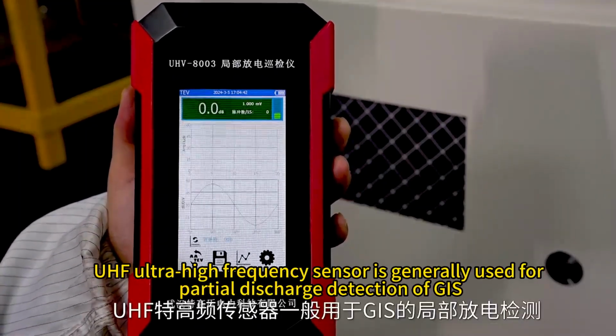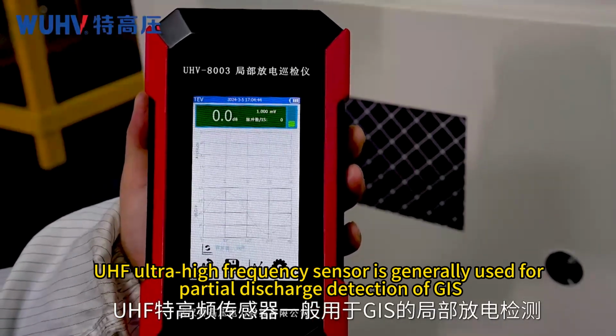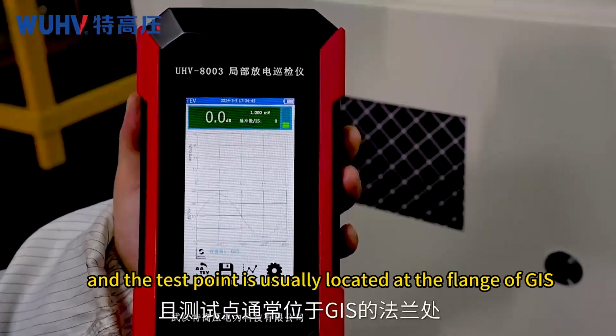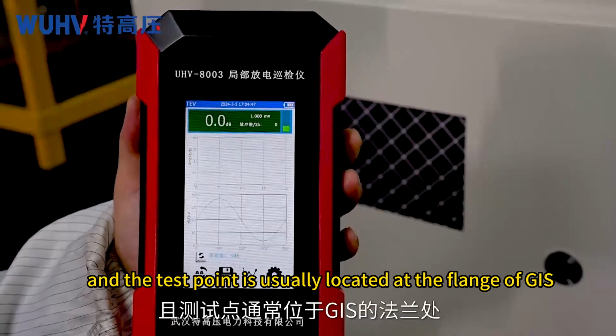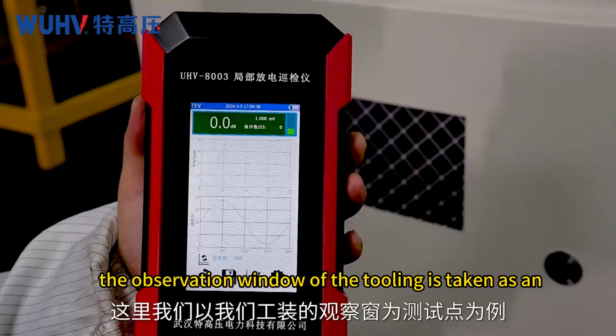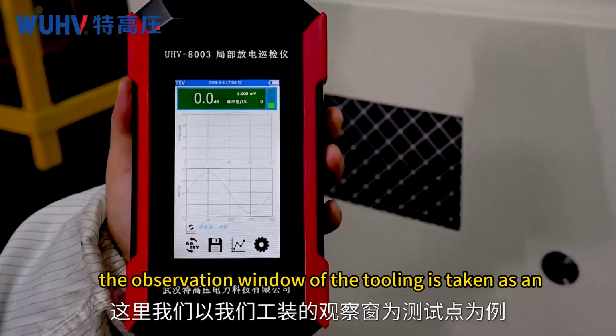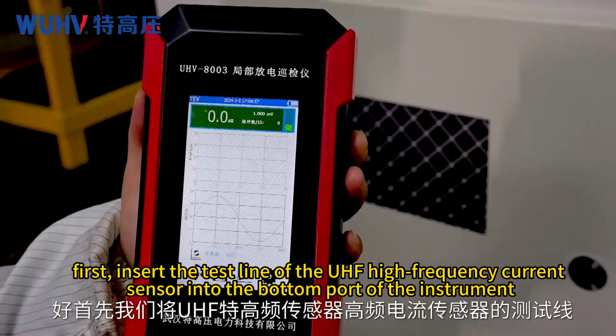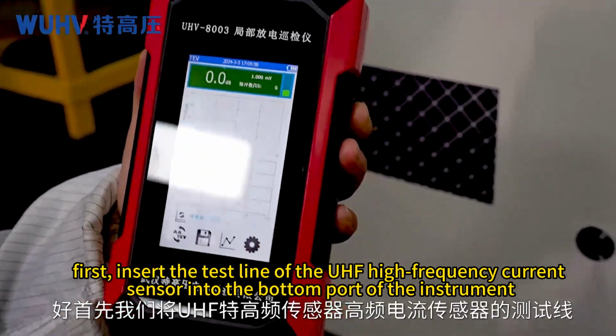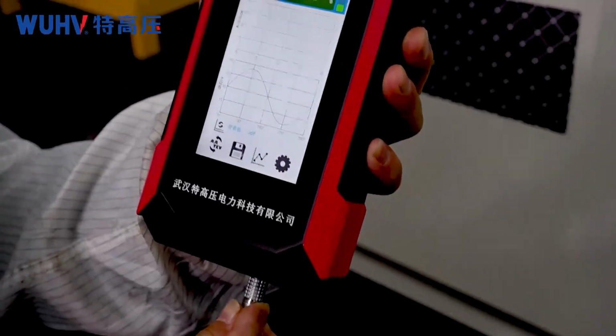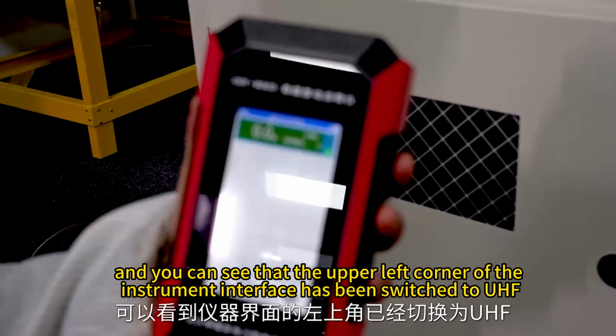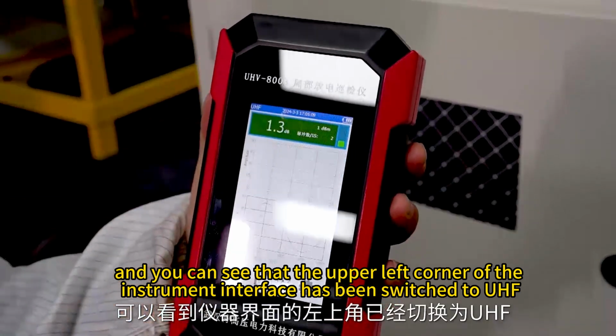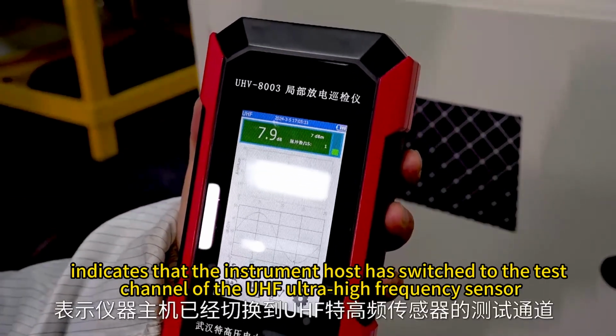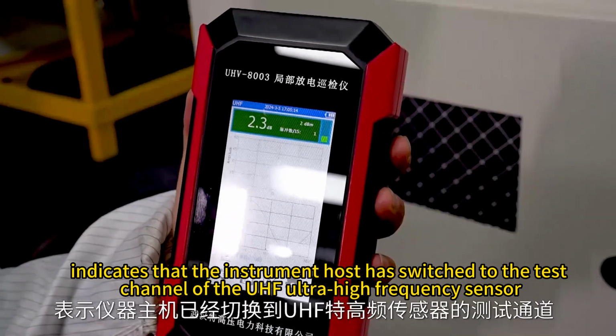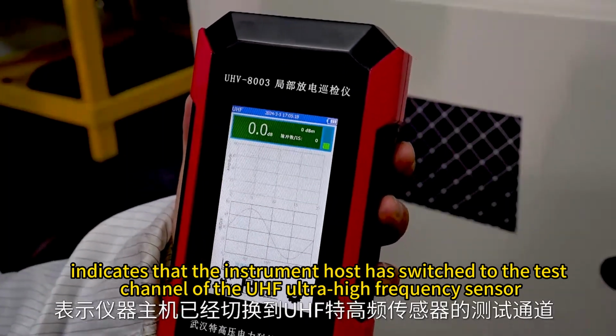UHF ultra-high frequency sensor is generally used for partial discharge detection of GIS, and the test point is usually located at the flange of GIS. Here, the observation window of the tooling is taken as an example of the test point. First, insert the test line of the UHF high-frequency current sensor into the bottom port of the instrument, and you can see that the upper left corner of the instrument interface has been switched to UHF. Indicates that the instrument host has switched to the test channel of the UHF ultra-high frequency sensor.